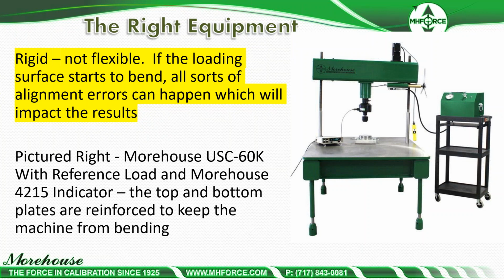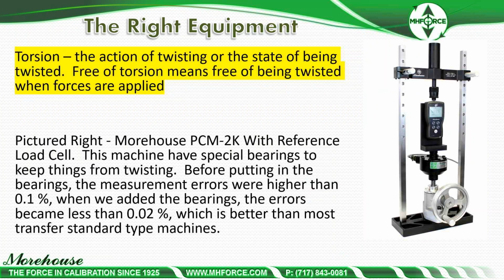This is a newly designed USC 60K with reference load cell and Morehouse 4215 indicator. Top and bottom plates are reinforced to keep the machine from bending. So very rigid. Our older machines bent, we reinforce them. Newer machines have very, very low bending. And remember I said the other thing is torsion. The action of twisting or the state of being twisted. Free of torsion means free of being twisted when forces are applied. That is all done in here.